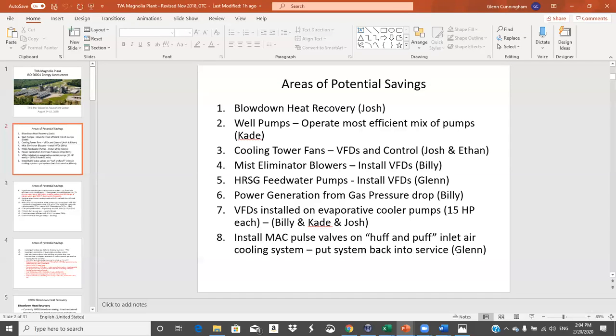And it depends on the load on the tower for the entire year, because in the summertime when it's hot and humid, you probably have to run them all at full. But at night it cools off a little bit, and so you can modulate them down a little bit, up and down. And so it's that savings integrated over the whole year that will determine what the payback is. So anyway, that's what that's talking about.